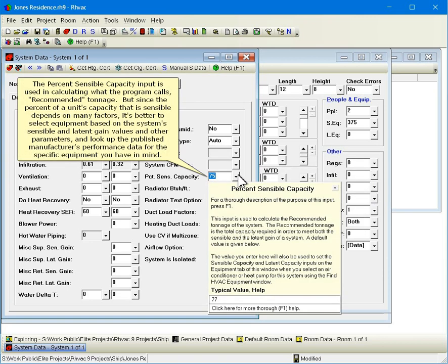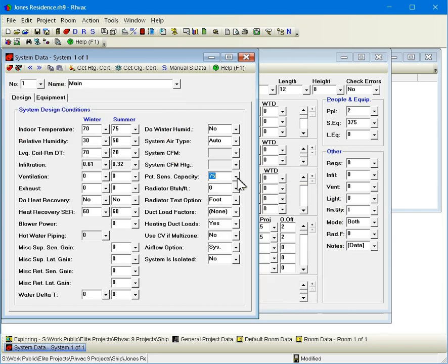The percent sensible capacity input is used in calculating what the program calls recommended tonnage. But since the percent of a unit's capacity that is sensible depends on many factors, it's better to select equipment based on the system's sensible and latent gain values and other parameters and look up the published manufacturer's performance data for the specific equipment you have in mind.